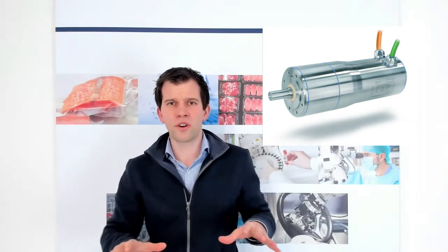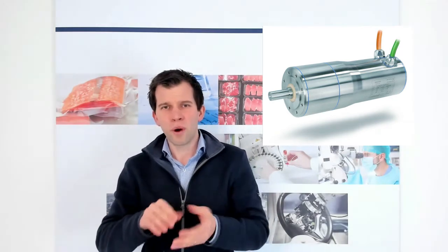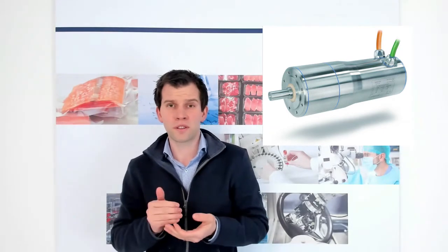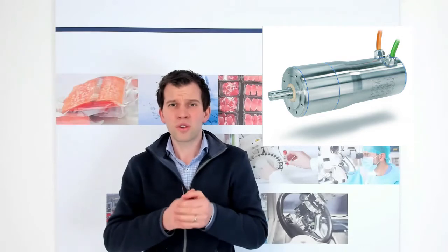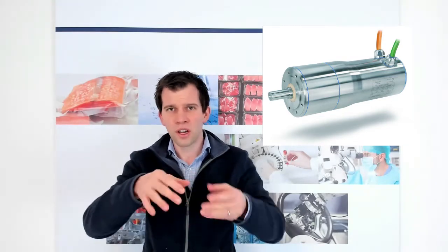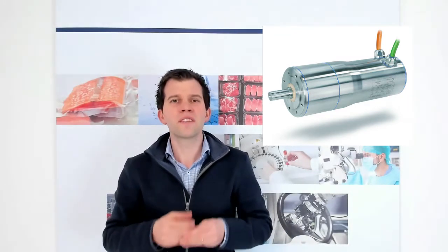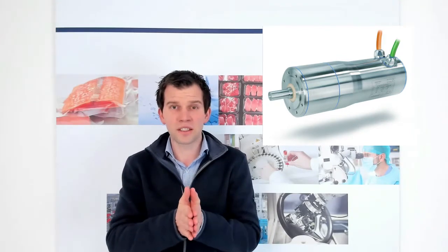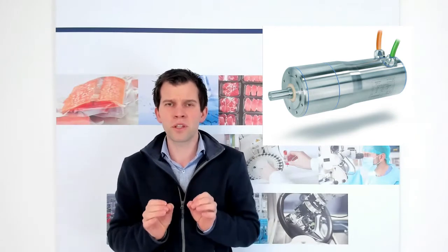For example, you have a very clear surface, a very low roughness, less than 0.8 micrometers. You have no dead cavities around the motor. It's all round, so the water can drop down off the motor. You can clean this motor very easily. As you see, the interconnections are linked with a sealing. Therefore, it has a very demanding sealing principle.